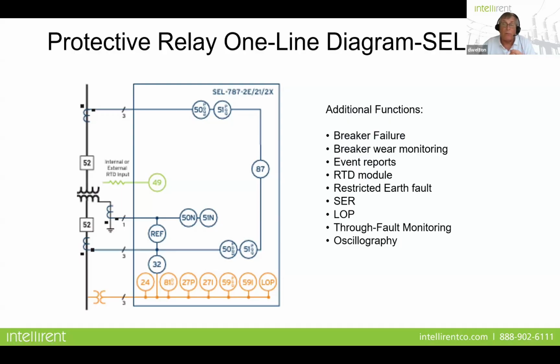First of all, you have a breaker failure element. So if there is a fault and you try to isolate the transformer and the breaker doesn't open, you've got to have some kind of a backup means to isolate the transformer. So that would be breaker failure. Breaker wear monitoring: Schweitzer relays actually will count the number of times a breaker operates that's servicing the transformer. Event reports, RTD inputs if you want to do thermal measurements, restricted earth fault. SER is sequence of events. So in the event that you do have a fault or a series of faults, it will date and timestamp and give you the values that caused the relay to trip.